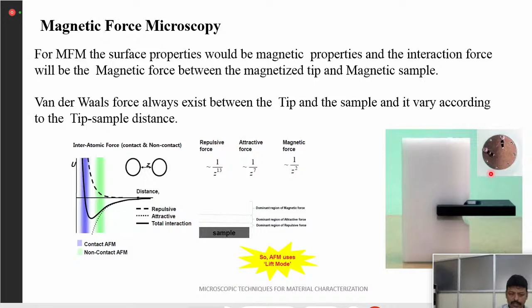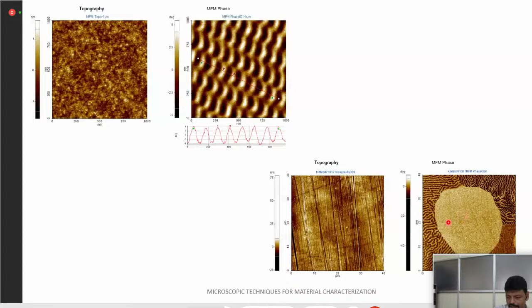So you can use it as magnetic force microscopy. If you want to study the magnetic force, the magnetic properties of your sample, you can use a magnetized tip. We will be changing the tip and doing the magnetic properties analysis. You can see these interesting images. The first one is the topography of the sample, but when you go for phase, you can see an array where one area is magnetized and the other area has less magnetic property. Like that, you can observe each sample. Here, this is a mix of materials, so qualitatively you can identify how each material is placed in this kind of phase image.